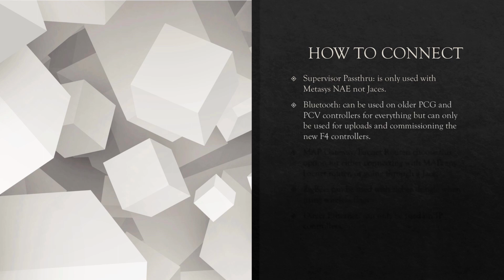So, connection problems. Let's talk about connection problems. There's a couple of ways to connect to the controllers, right? Supervisor pass-through is only used in Metasys NAEs, not Jaces. And even going through a Metasys NAE, you cannot connect pass-through to an FX field controller. It won't let you do it, okay? So this is only for Metasys. So not for most of us. That's only the Johnson Controls guys.